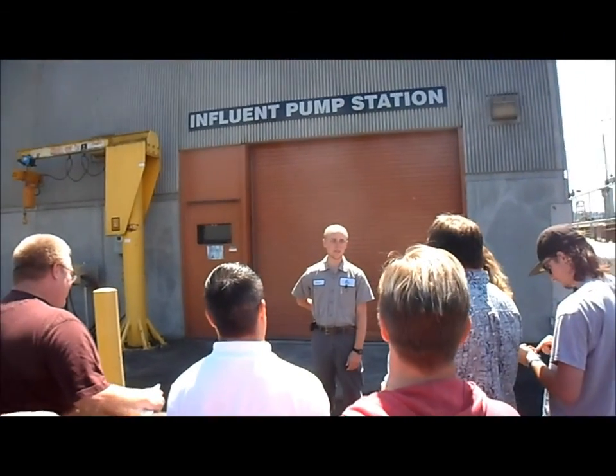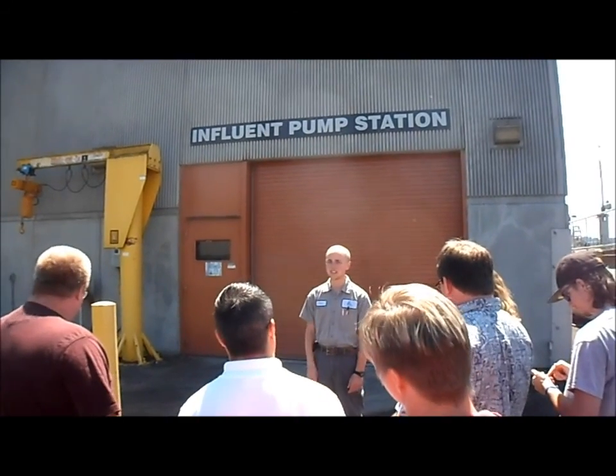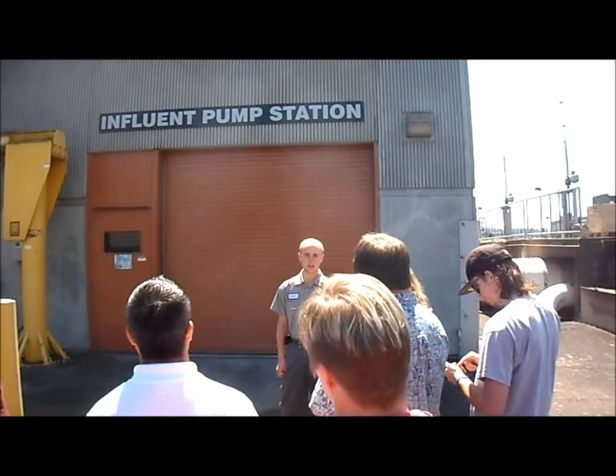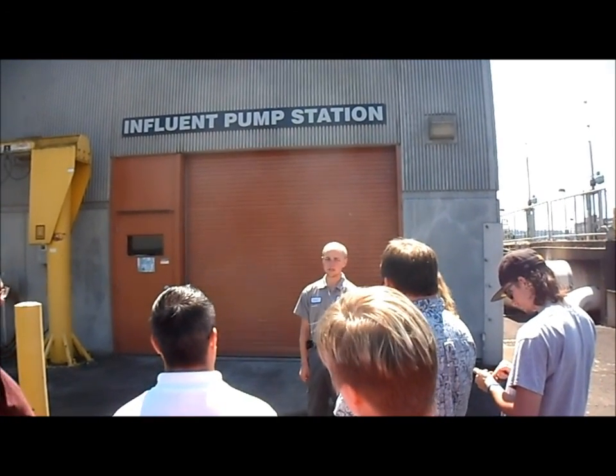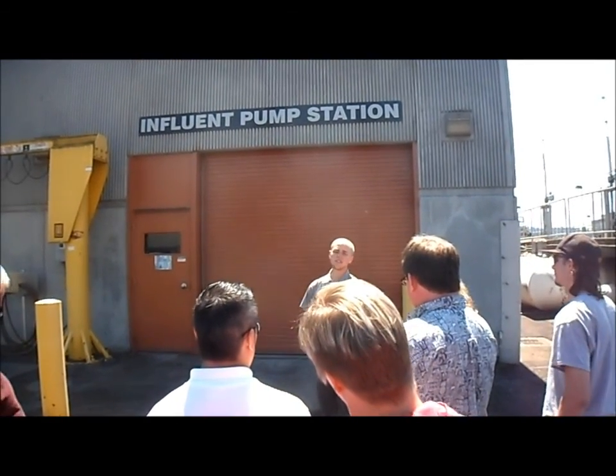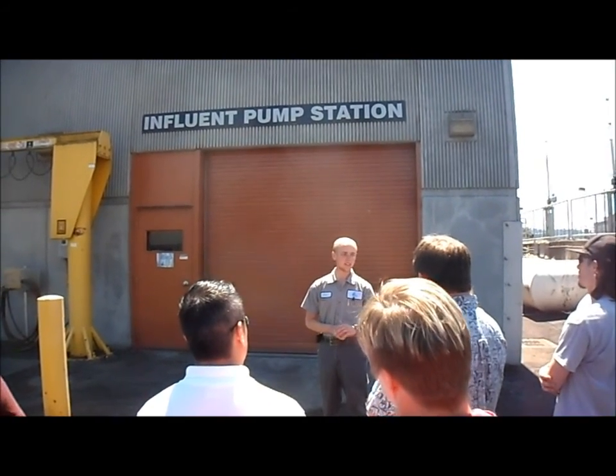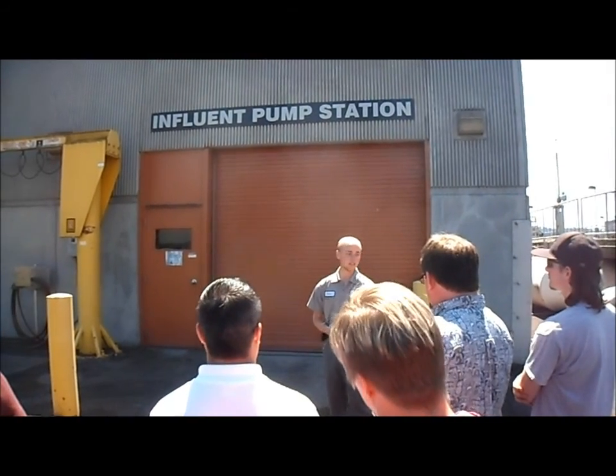We treat from 3 cities: Tri-City plant, Oregon City, West Linn, and Gladstone. We have 5 influent pumps. The 3 big ones do 12,500 gallons a minute, and 2 smaller ones do 5,000. They're running on VFDs, but we tell them to maintain a 6-foot level in the wet well, so they ramp up or down when the level goes up or down.